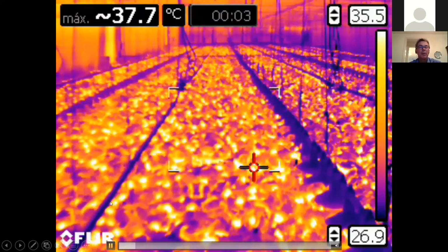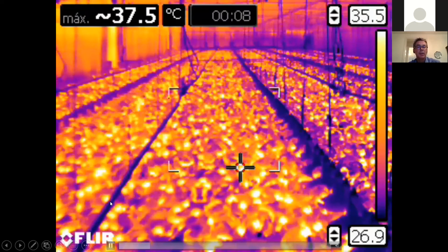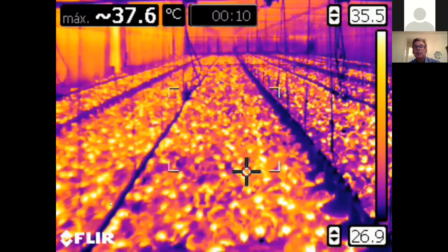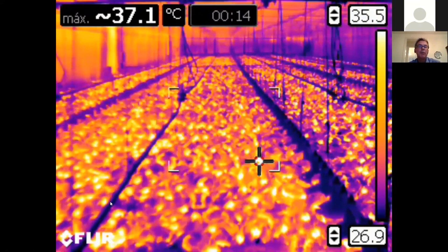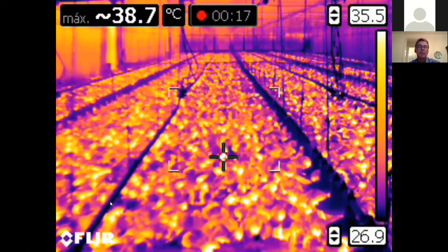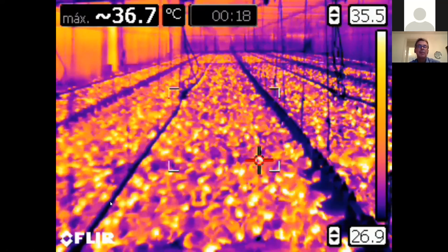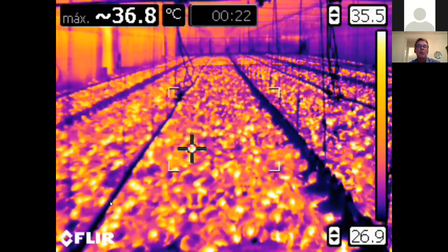With a thermal camera, the whites, the yellows, the oranges indicate high surface temperatures. The blues, the purples, all indicate cooler surfaces. So within about 45 to 50 seconds, we quickly see that feather temperatures change. And that's an indicator to me that with the extra air exchange, we're removing more sensible heat.